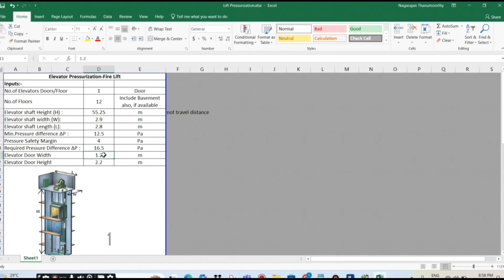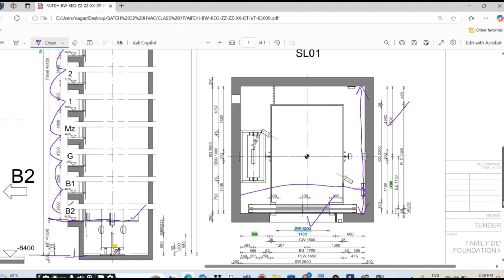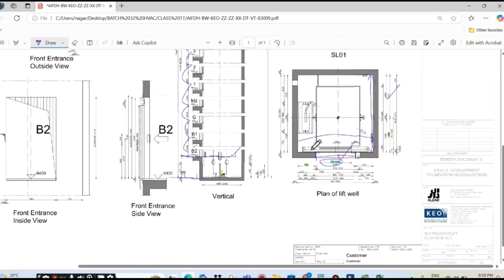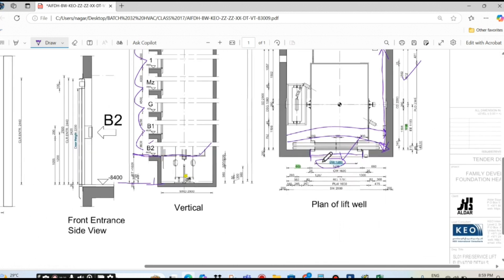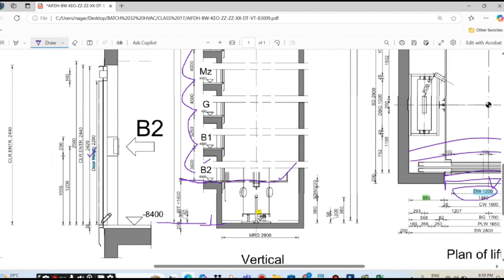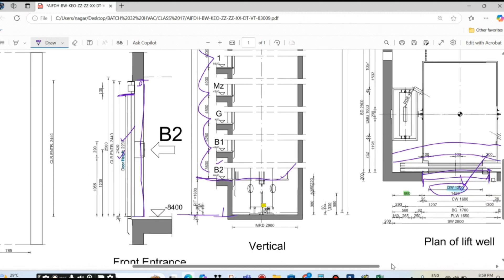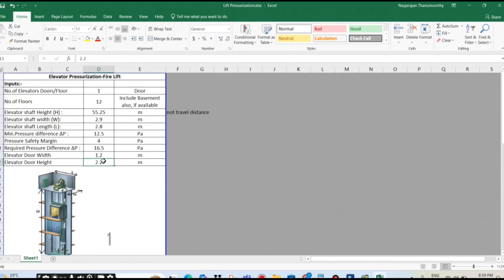So elevator door width. Now we discussed about the shaft only. Now coming to elevator door. So the width we have to consider only the internal door width from here to here. So this one, like you see, is 1,200. This is the elevator door width — we should not consider the full internal shaft, only the elevator door width from here to here. And elevator door height means, here you see the door height we have given from the internal finished floor level to the top level. This is the door height: 2,200. And door width is 1,200. So these two dimensions we have to add here: 1,200 and 2,200.